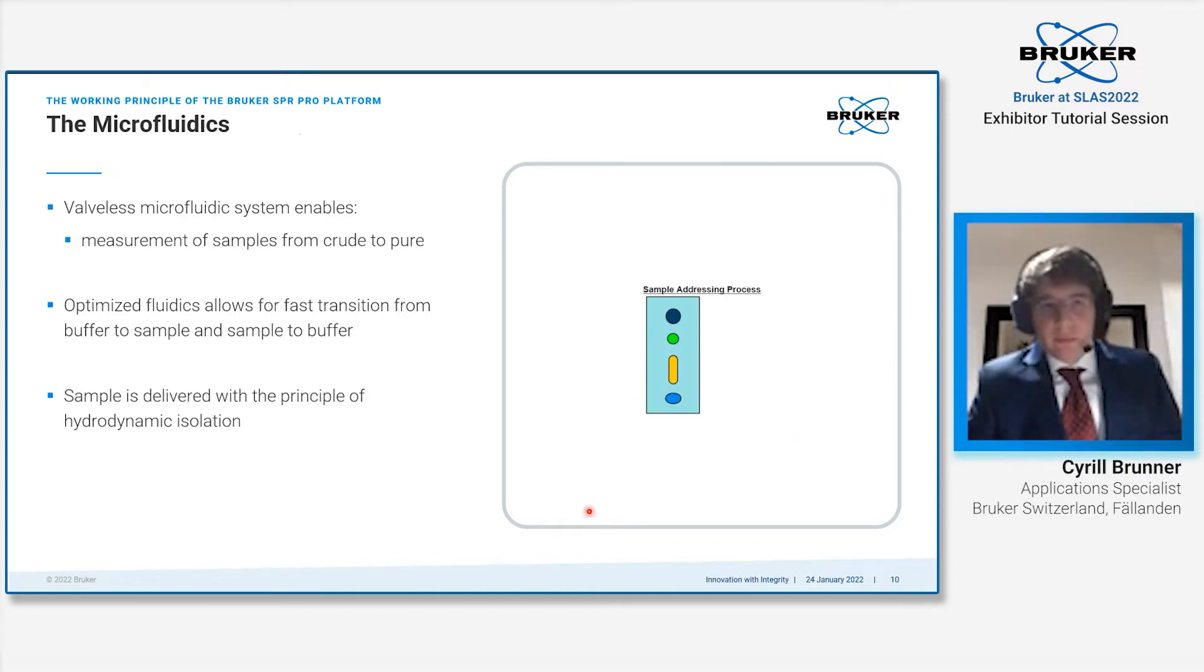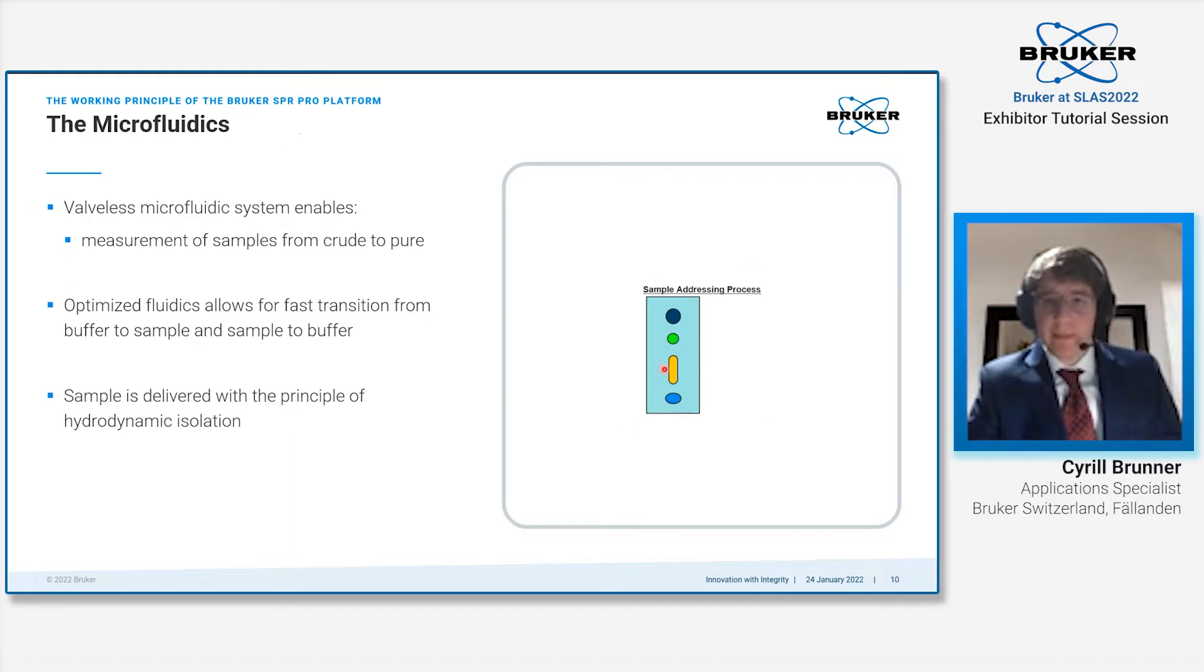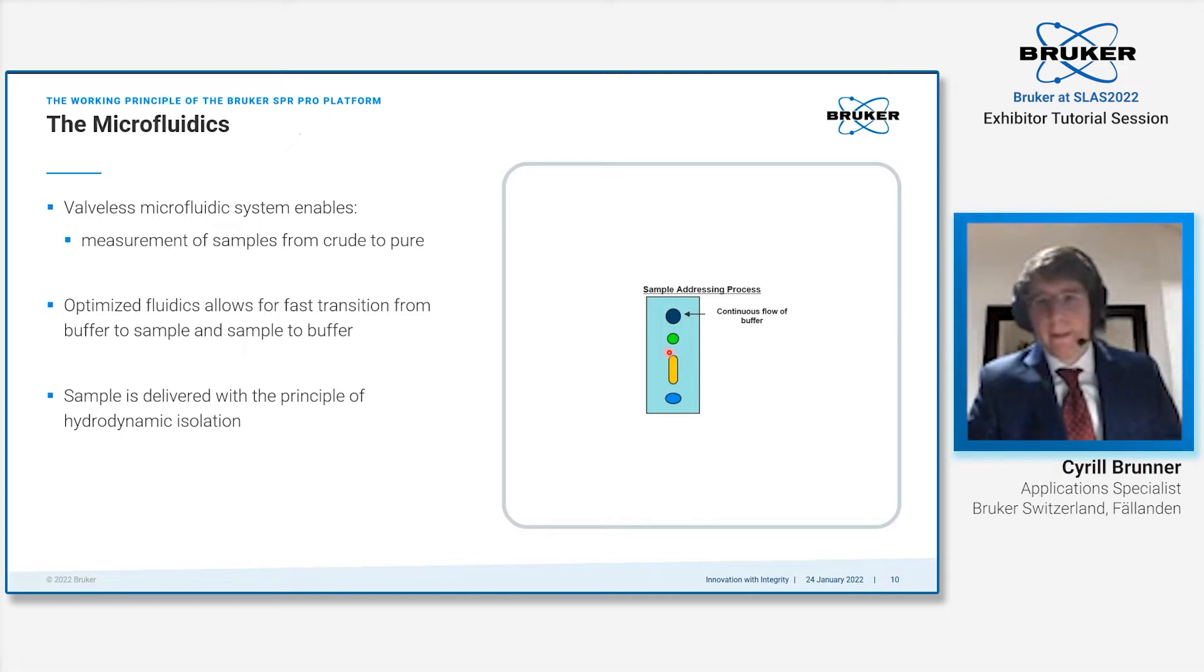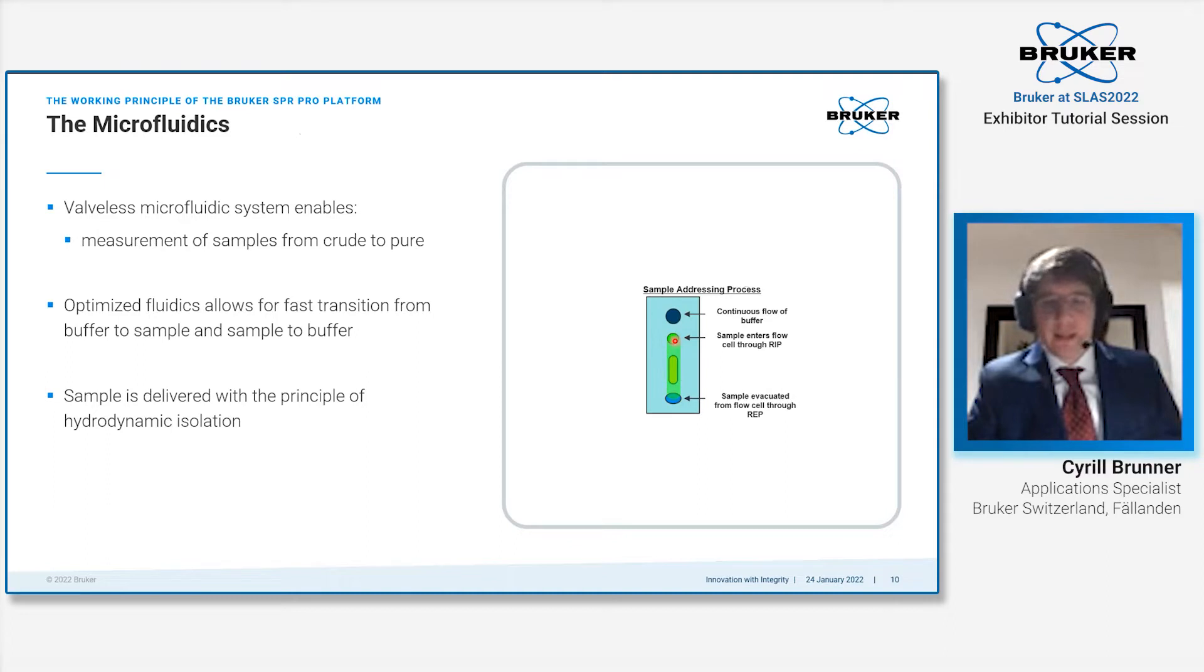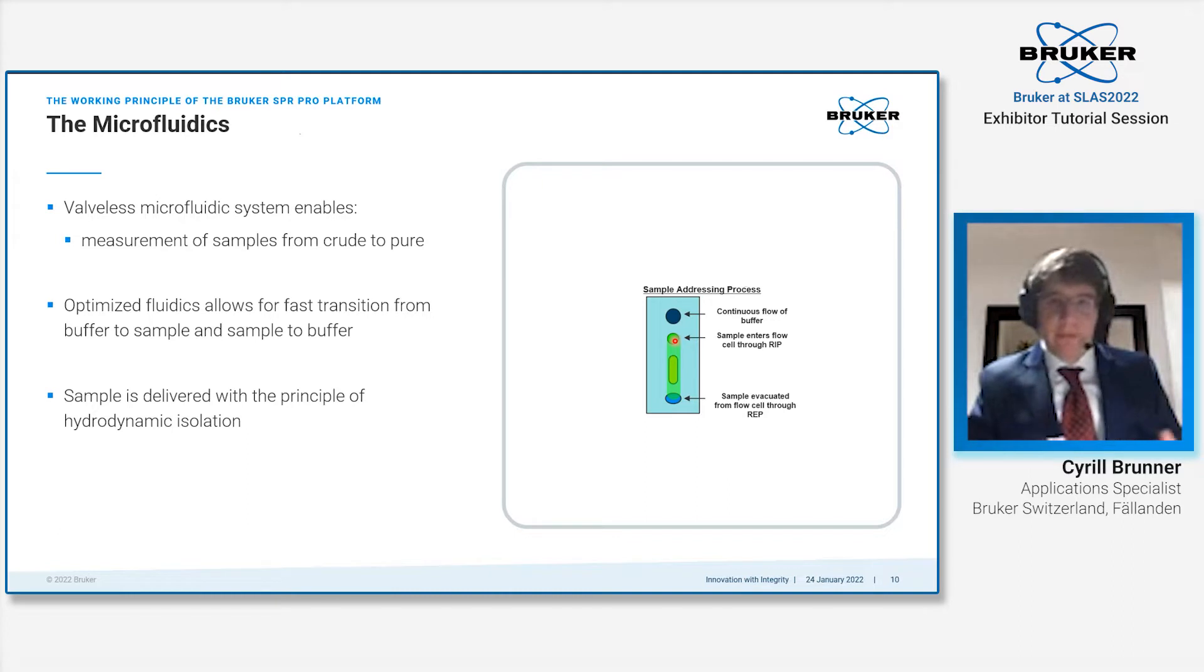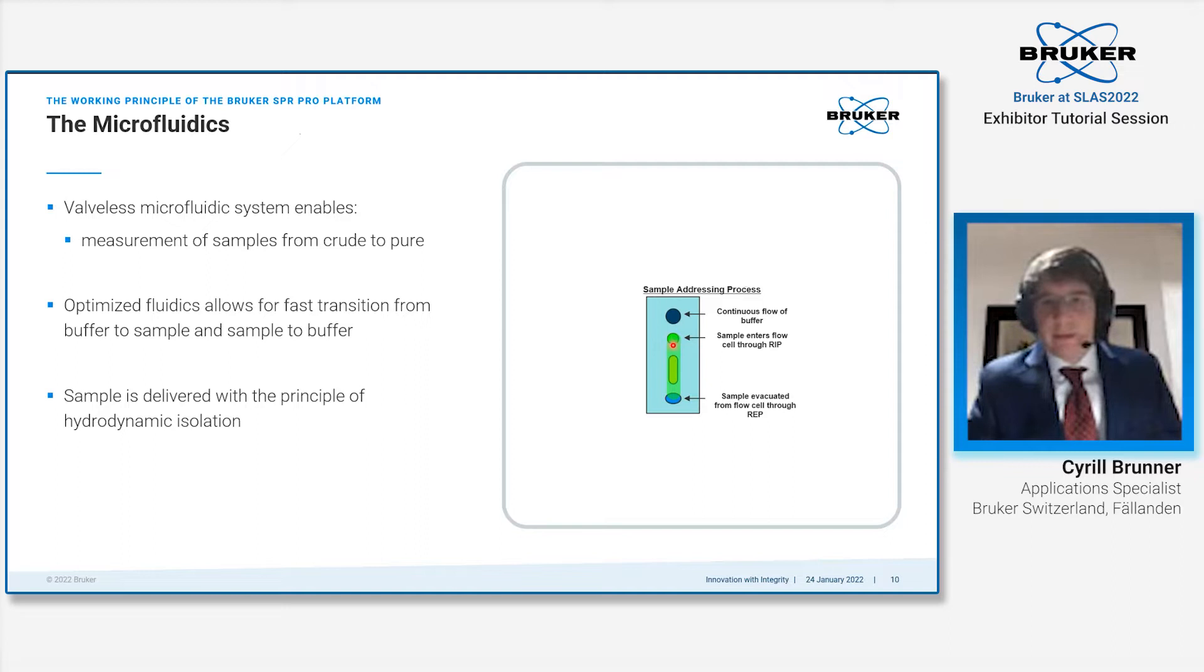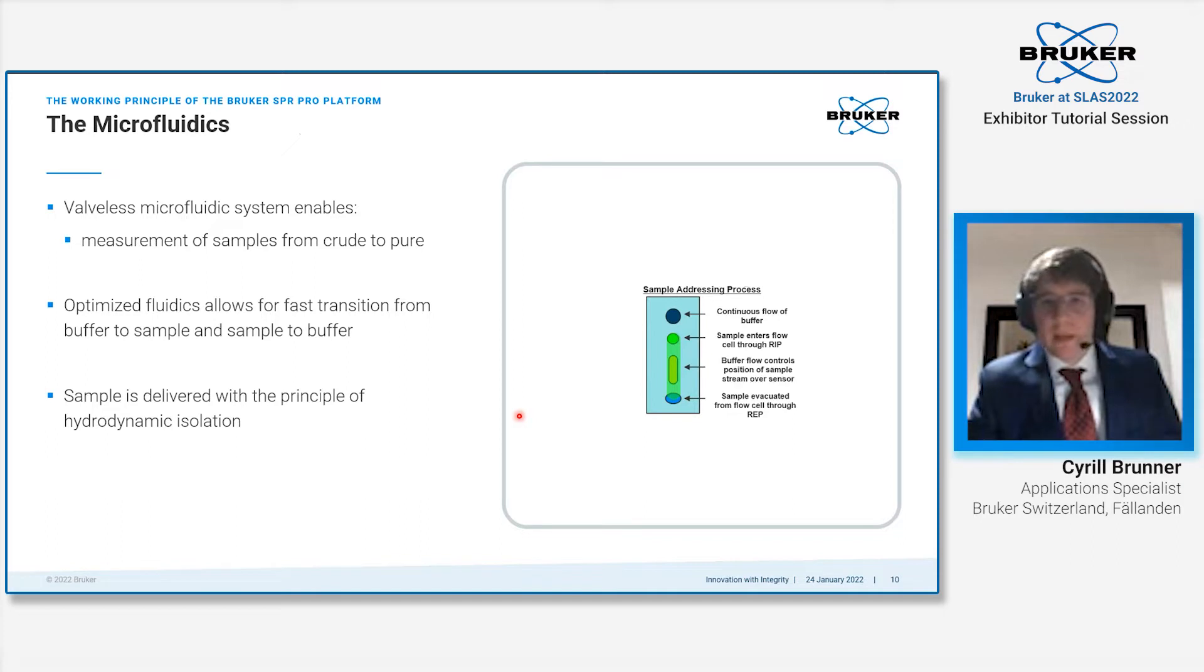The reason we can do this setup in a valveless manner is that we use hydrodynamic isolation as our working principle. You see here the setup of the measurement spot, then there's a buffer inlet which gives you a continuous buffer flow. When the sample is injected, it is guided within the flow cell by the buffer stream. The buffer stream acts like a guiding rail, preventing any usage of valves. Then you have an evacuation port where the whole sample is taken away.